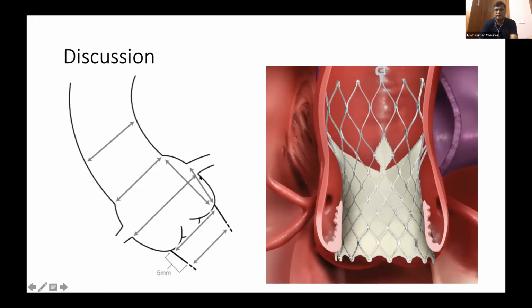The sinus of Valsalva diameter should be at least 2 millimeter more than the size of the valve you are using. So if you're using a 23 millimeter valve, it should be at least 25. If you're using a 26 millimeter valve, then it should be at least 27 or 28. If you're using a 29 millimeter valve, then the size doesn't matter much. It is either 29 or 30, but if you're using a 34, then it is 31.